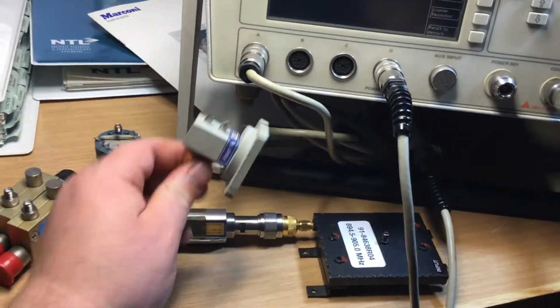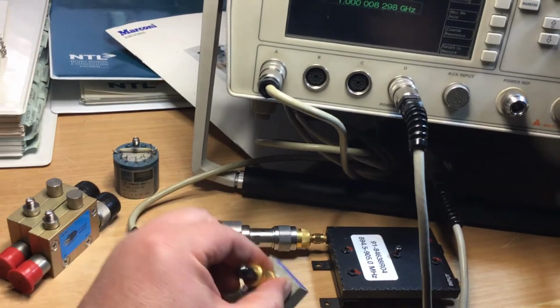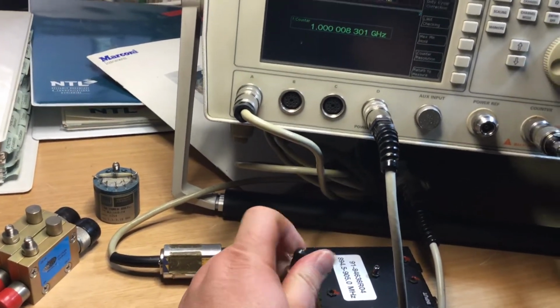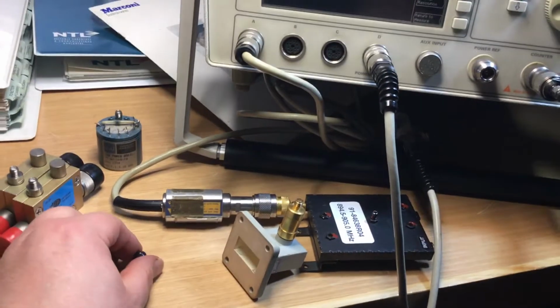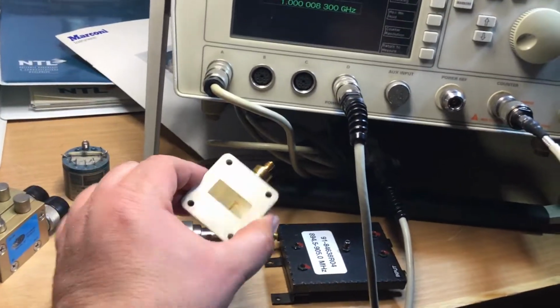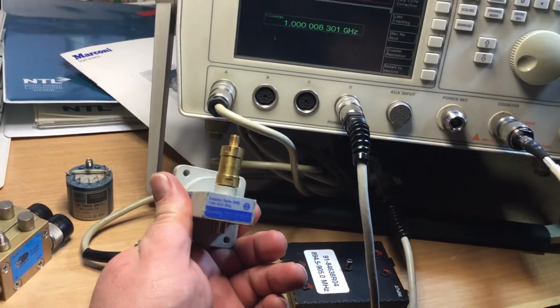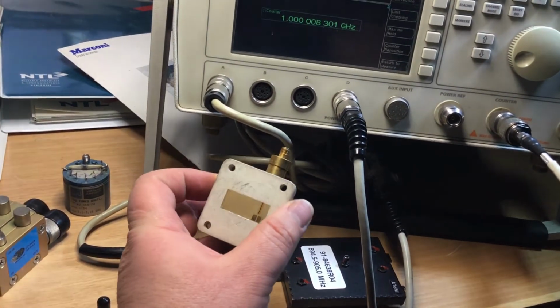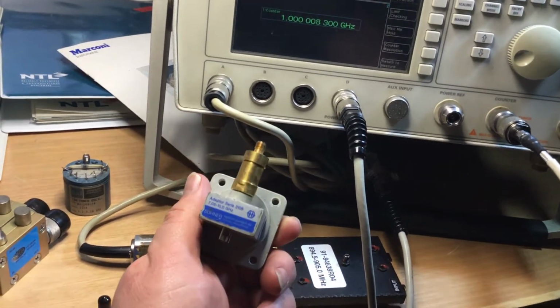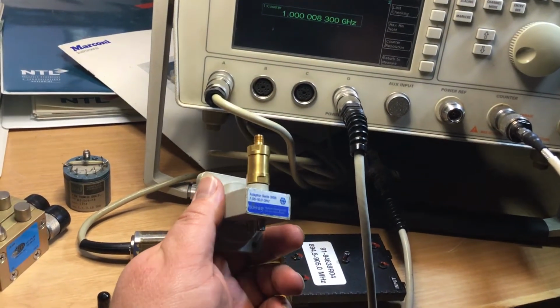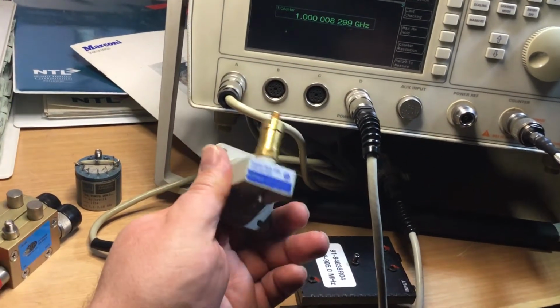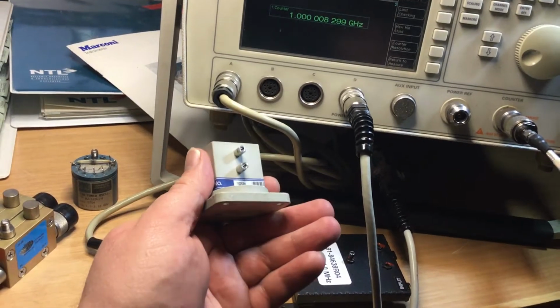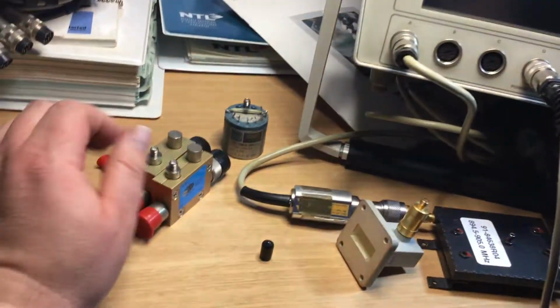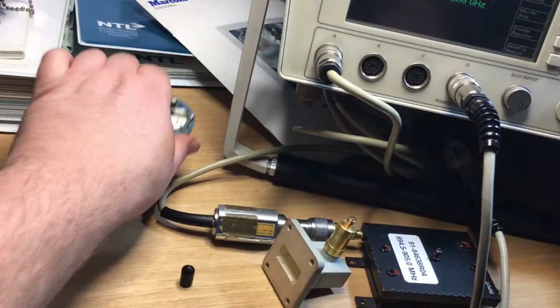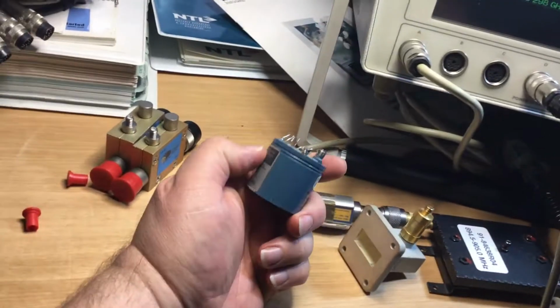And again, we've got things like this where we can transfer coaxial feeders from the outputs into Waveguide. So if we've got equipment that uses Waveguide feeders, for example, then we can transfer coaxial into Waveguide. That's what this does. So what's called a coaxial to Waveguide transition. And this is what's in these test sets that generates the signals.